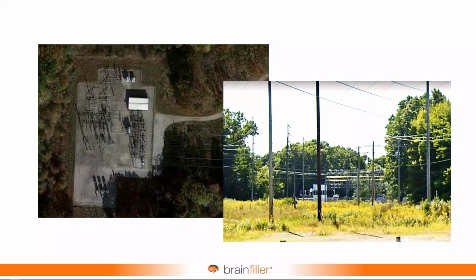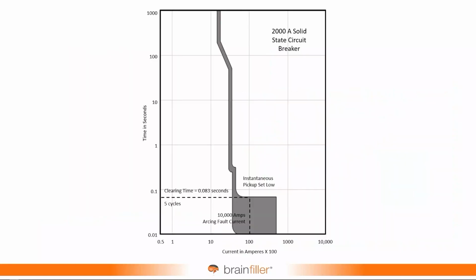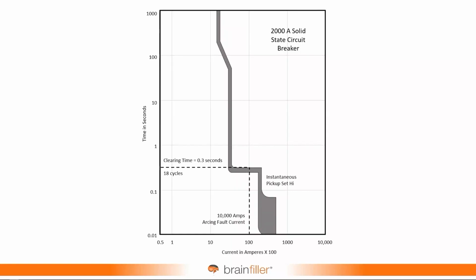Well, I eventually moved on and headed up the transmission short circuit studies group for the whole system. When this substation that I'm showing here came online, the fault current in the area jumped dramatically. And that could have an impact on equipment duty. It could have an impact on the incident energy. But also, there were cases in the area where we would retire substations that were old, and you could see fault currents reduce as well. So there are a lot of moving parts to an incident energy analysis, including the device settings. If we have a device with this current and these settings, and then the settings change, guess what?